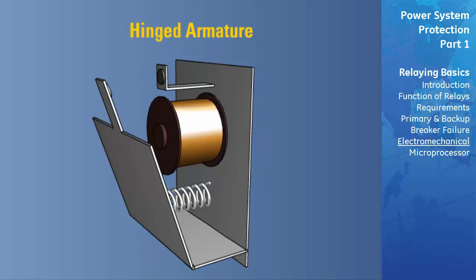The hinged armature construction, which also includes the cantilever and beam type of construction, consists of a flat plate or bar type of armature, which pivots at a fixed point when attracted to the pole face of an electromagnet. The armature carries the moving portion of the contact, which meets a fixed contact when the armature is picked up. An advantage of the plunger and hinged armature style of construction is that they have no inherent time delay, hence they are used for functions which require instantaneous operation.